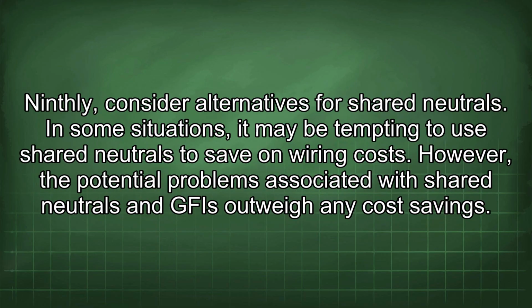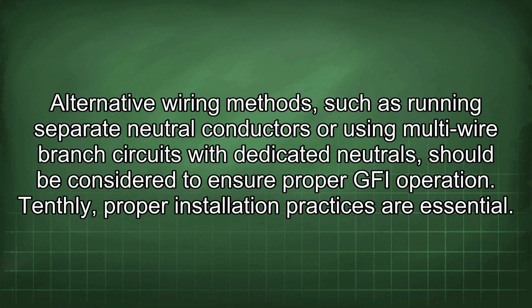9. Consider alternatives for shared neutrals. In some situations, it may be tempting to use shared neutrals to save on wiring costs. However, the potential problems associated with shared neutrals and GFI outweigh any cost savings. Alternative wiring methods such as running separate neutral conductors or using multi-wire branch circuits with dedicated neutrals should be considered to ensure proper GFI operation.